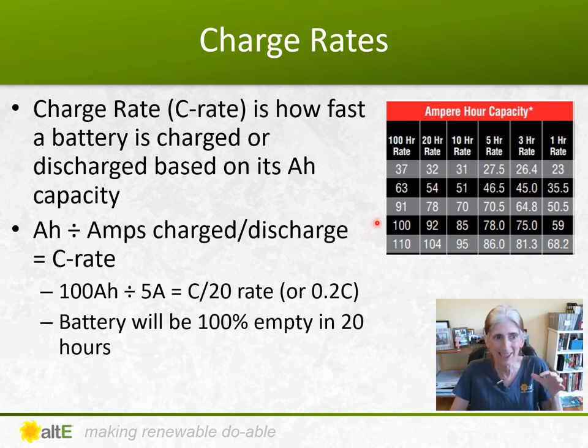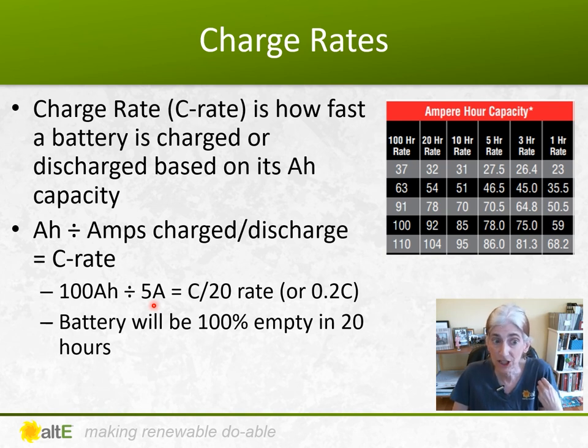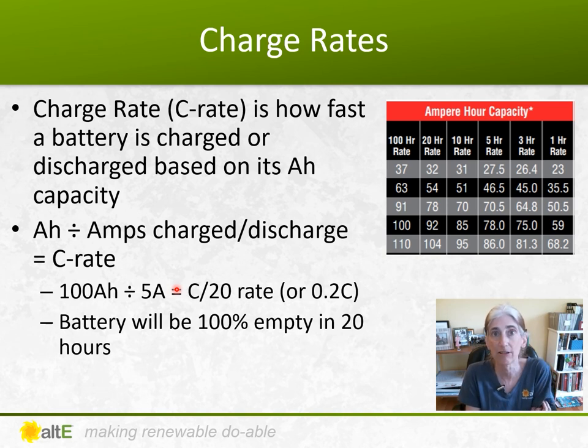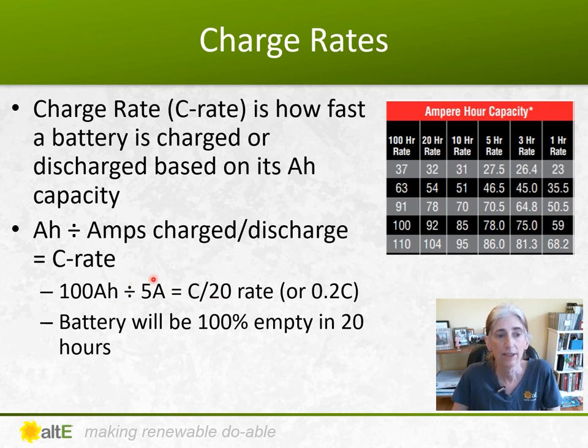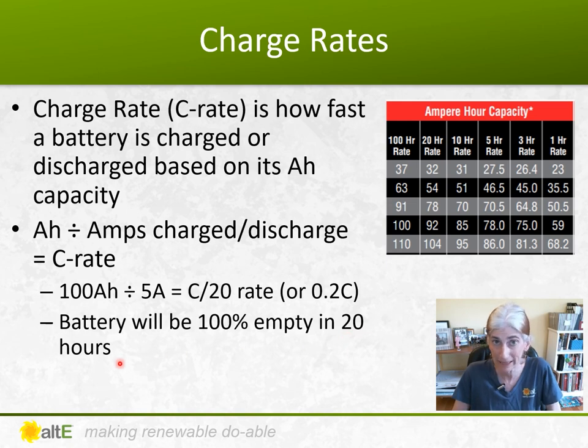It's a bit of a balance because your charge rate is based on the capacity. Here's an example: a 100 amp hour battery at 5 amps charging or discharging is a C20 rate, sometimes written as 0.2C. That means you're doing 20% of the amp hour capacity per hour — so drawing at 5 amps, the battery will be completely empty in 20 hours.